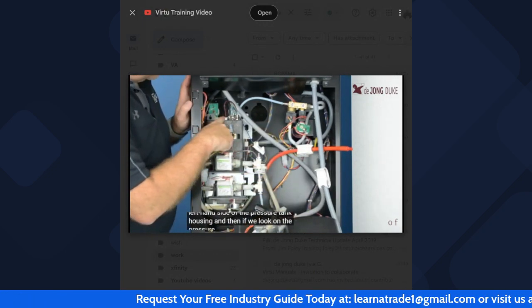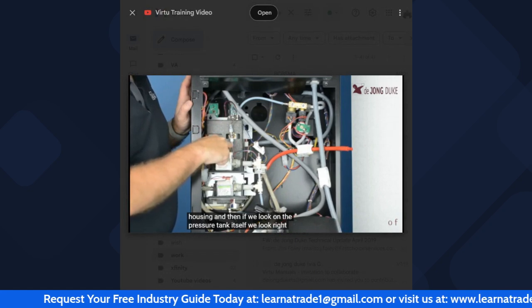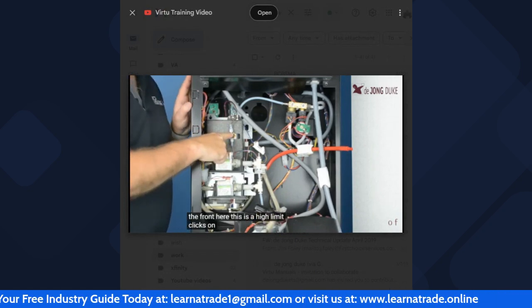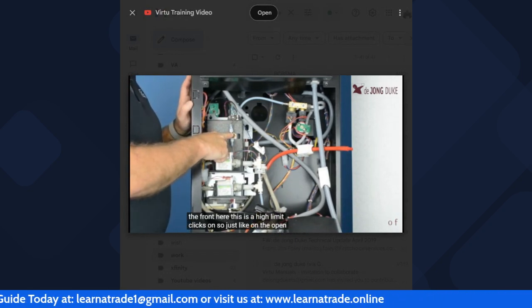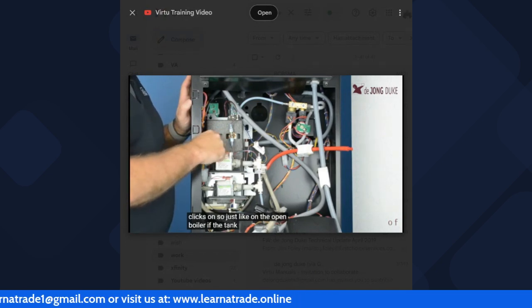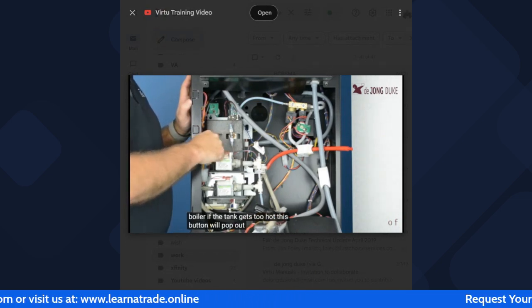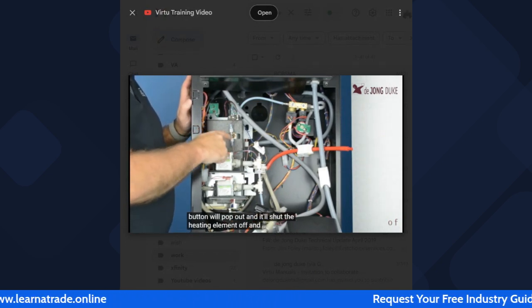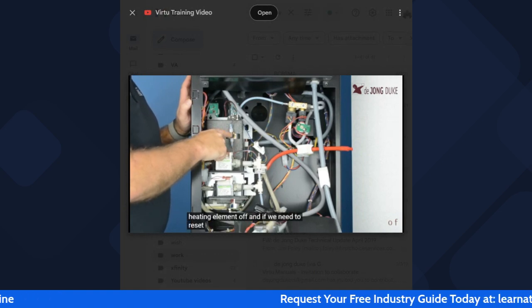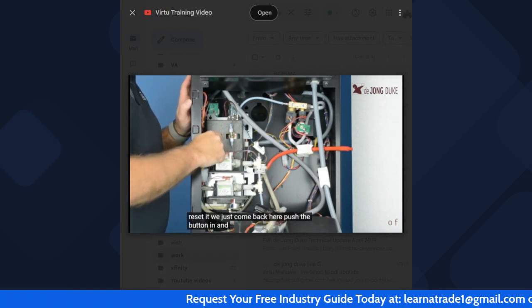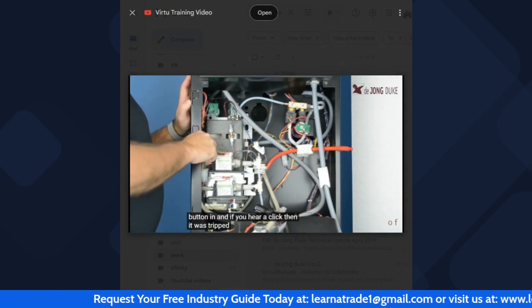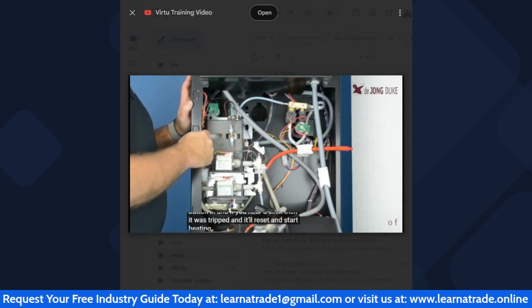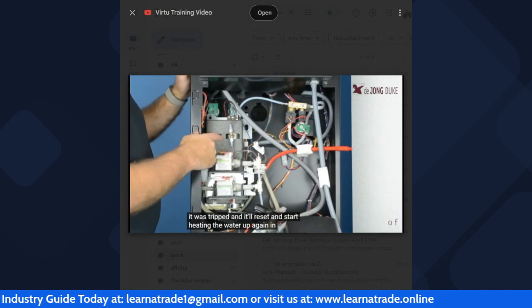And then if we look on the pressure tank itself, right on the front here, this is a high limit Klixon. Just like on the open boiler, if the tank gets too hot, this button will pop out and shut the heating element off. If we need to reset it, we just push the button in, and if you hear a click, then it was tripped, and it will reset and start heating the water up again in the pressure tank.